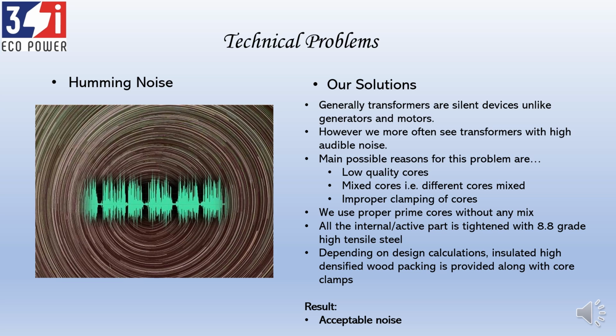if you are supplying 100 transformers distributed over the network, after 10 or 15 years there may be a slight loosening of the nuts because of the magnetostriction effect and the vibrations caused. Sometimes these nuts may fall onto the transformer core and coil assembly, and the transformer may fail. It is not very often, but there is still a chance of 1 in 1000. These things are eliminated by properly tightening with 8.8 grade steel. Once tightened, high tensile fasteners cannot just be loosened like that. You have to use a torque wrench to loosen them.